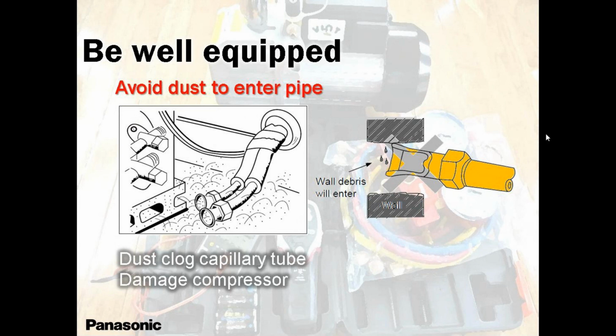Brazing. I'm sure everybody goes through a brazing certification or class in your area, like here, what we do. And you need to set the correct flame. And also, when you're using brazing, always remember to use nitrogen to get rid of this oxidization. So at least a few ounces, you flush while you're brazing, you'll be good. I mean, not ounces, PSI. 5, 10, 15 PSI, you're good. Slow flow. You know what I'm talking about. So make sure it's nice and clean. Look at the difference without nitrogen and with nitrogen.